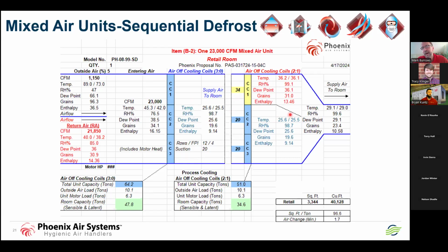So the condensate that comes off of that top coil, it's got its own drain pan. I don't want that condensate to hit coils 2 and 3. There's a drain that goes right to the bottom of the unit. When this thing is done defrosting, the top one turns blue, so it's active, or it's at the colder temperature. The second coil then drops out in its defrost, and it just repeats this all day long.